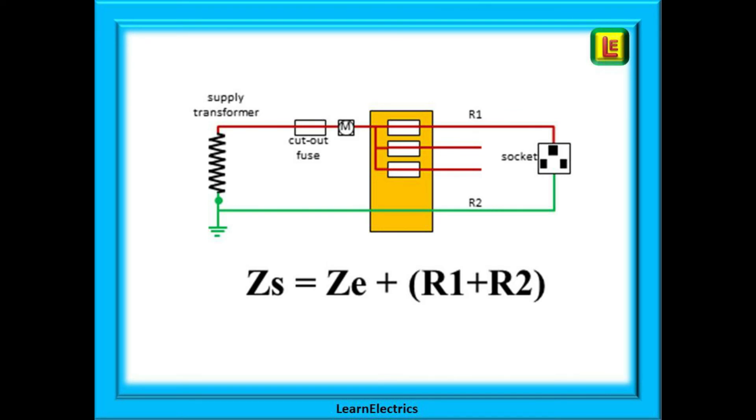So recalling Ohm's law, we know that if the resistance decreases then the current will increase. This means that the lower that we can make the resistance or impedance, then the greater the current that will flow. The greater the current, the quicker the fuse or breaker will disconnect the supply. The faster the disconnection time, the more chance a person has of surviving the electric shock.